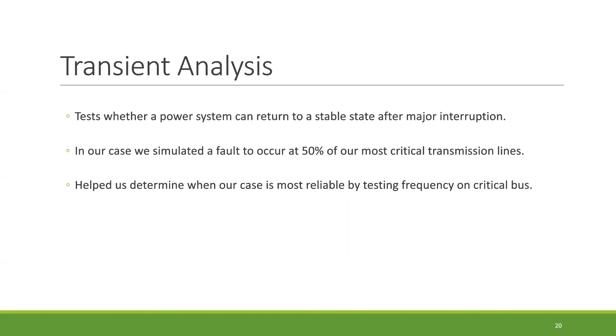So these two graphs show our frequency result after adding the fault. The fault we inserted in this case was a 3-phase fault on a 765 kV line from Long Beach to Huntington Beach. This fault was applied at 50% of the transmission line. So on the left side, you can see the case converges and it shows the frequency is stable at 80% renewable penetration. And that is the last time the case is able to stabilize. On the right side, the case is at 81% and diverges. The large dip in frequency makes it harder for the generation to stabilize and causes it to diverge.